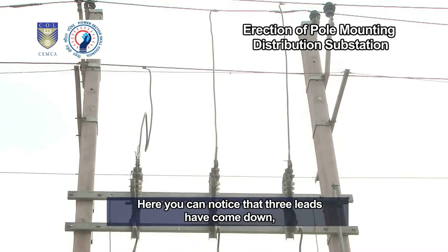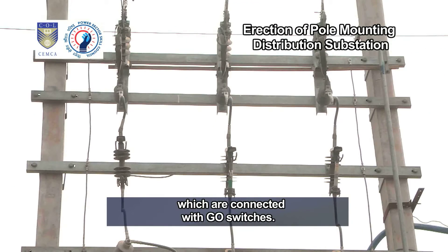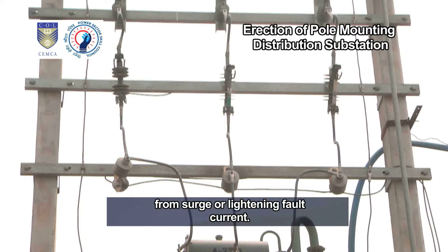You can notice that three leads have come down which are connected with GO switches. Below the GO switches, drop-down fuses are fixed along with barriers. Lightning arrestors have been fit below the GO switches to protect the system from surge or lightning fault current.